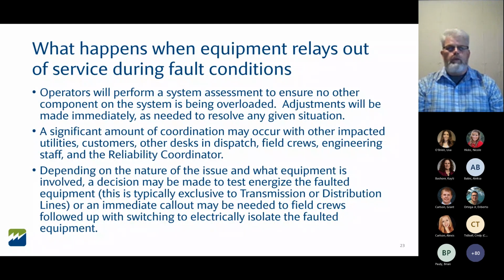So there's a whole bunch of coordination that has to happen between the control room, the dispatch center, and the field, along with other utilities, customers, neighbors, engineering staff. The RCs, reliability coordinators, may need to be involved. And depending on the nature of the issue and what equipment is involved, a decision will have to be made. Are we going to test that piece of equipment? Maybe it requires a manual test.